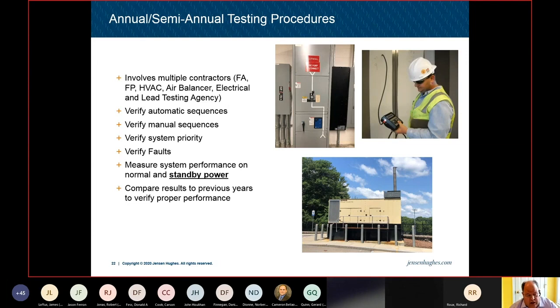That includes taking belts off of fans to make sure the fans are running but they're not pushing any air movement. We want to make sure we're not showing that fan is on and running. So there's a lot of things that go into that, and the lead testing agency can coordinate all those service companies to come in and do the tests that are needed. We also need to measure system performance on normal and standby power. So there's a lot of different things that go into it.